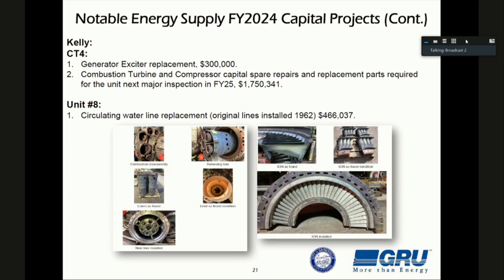These are large pipes with large flow. They see a lot of erosion, they see a lot of corrosion. We maintain them, we do NDE readings, we know what the wall thickness is. But Kelly Unit 8 piping, originally installed in 1962, is falling below that minimum wall thickness.